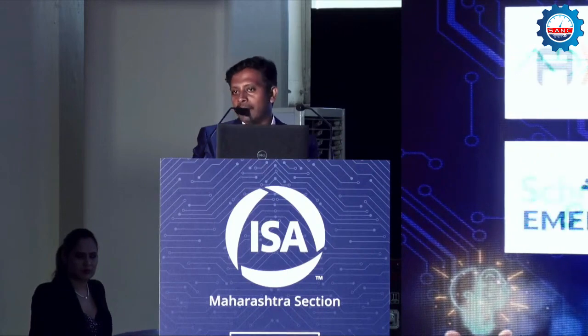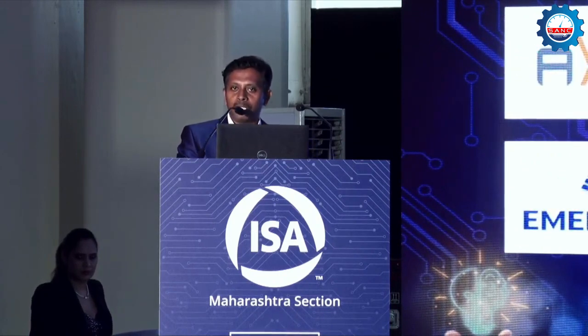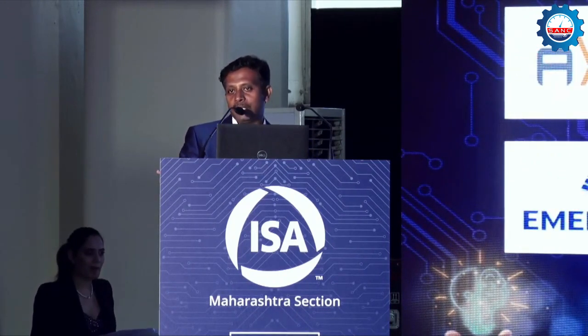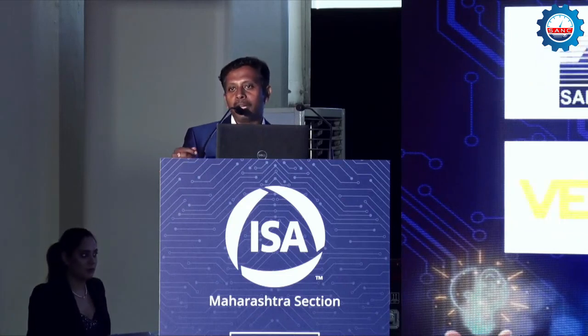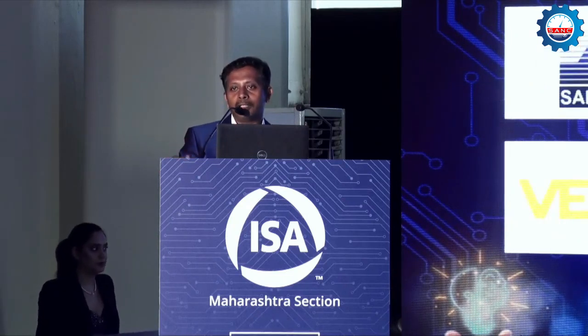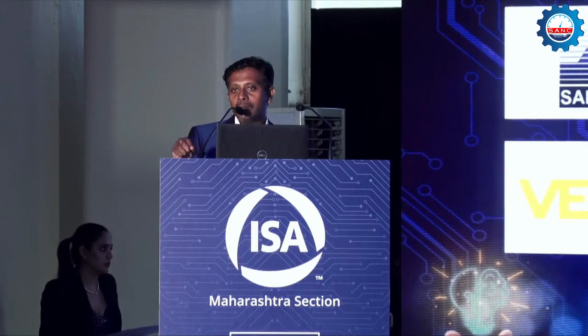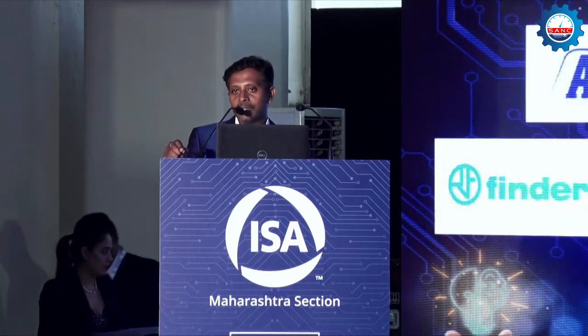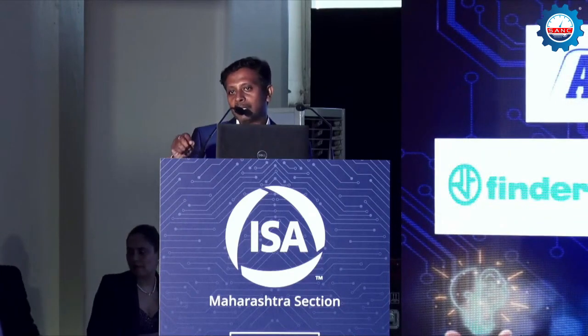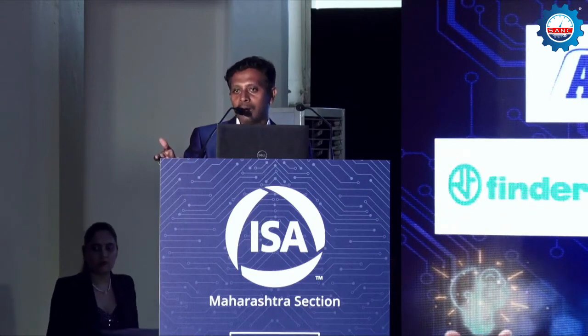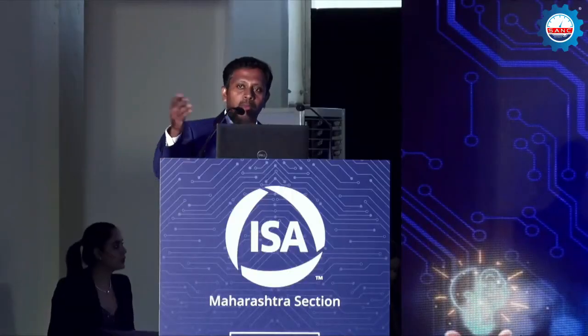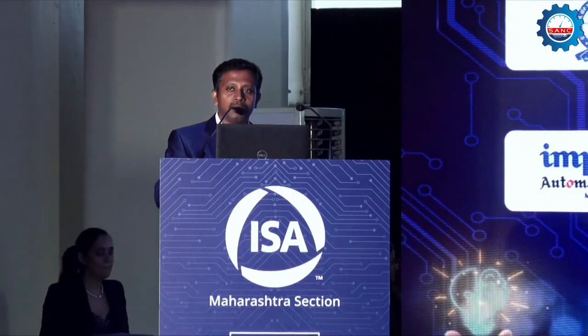No, the coat shield does not have any temperature limitation. The coat shield is not a physical one. What we are doing is electronically eliminating the error signals. To find the error signals, we have a physical construction: we introduce one more probe as a coat shield. That is also an SS rod, which measures the other currents created by the coatings. We analyze that and remove it in the electronic unit.